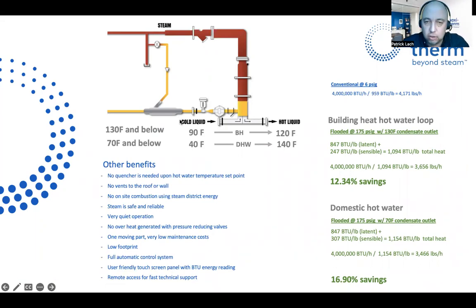So in your conventional system, typically you will work around 6 psi, because even if you're reducing the pressure between 15 and 10, you will never have 10 in the heat exchanger. You'll have a pressure drop through your steam control valve. So let's assume at full load, for a 4 million BTU process, just as an example, you will need 4,171 pounds per hour of steam, top right.